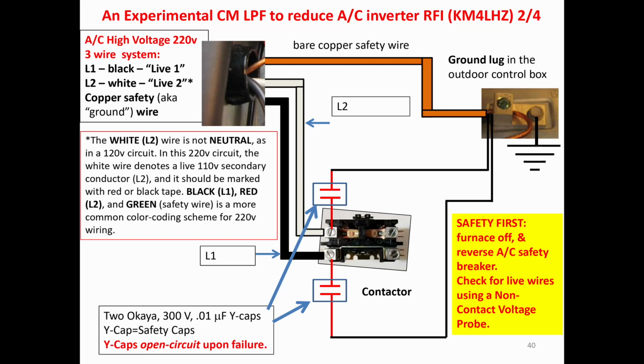to the compressor circuits. One thing: no one should try to do this unless they're comfortable. By that I mean you would need to turn the furnace off. You need to reverse the AC safety breaker, which by regulation is very close to the outside furnace unit. Of course, this is an outside furnace unit. And then you need to check to see if any wires are alive using a non-contact voltage probe. Then and only then can you attempt modification like this.